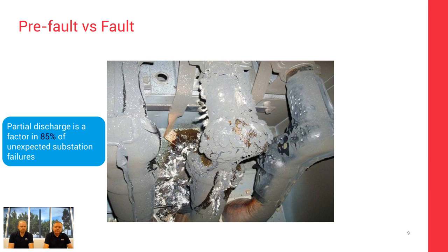If we're looking at this now where we've got the situation, we could have an outage that lasts particularly weeks or months longer. We've got to replace these components. We've got to start looking at the cleaning. Potentially what you have when you get a failure that goes into the bus bars, into other areas, is you get secondary faults. So that starts coming up. So we can be looking at multiples, 3-4 times the cost of that. Certainly one of the companies that has done a big study on this is Singapore Power. They looked at that cost and the savings that they were making were in that order of between 2-4 times the cost, possibly more than that at times, depending on the voltages that they're looking at with the cost of that you're saving.